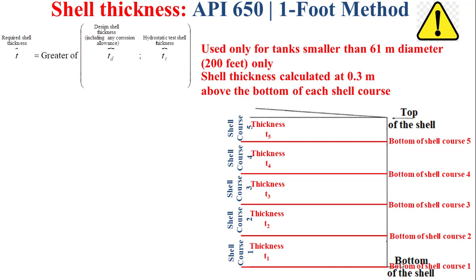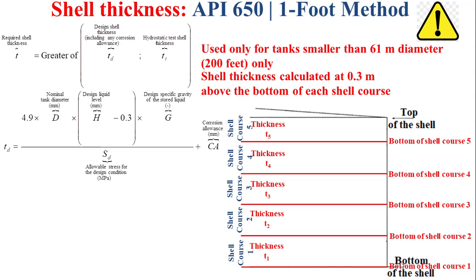The required shell thickness t is the greater of the design shell thickness td and the hydrostatic test shell thickness tt. The design shell thickness td is determined as a function of the nominal tank diameter D, the design liquid level h, and the design specific gravity of the stored liquid g.